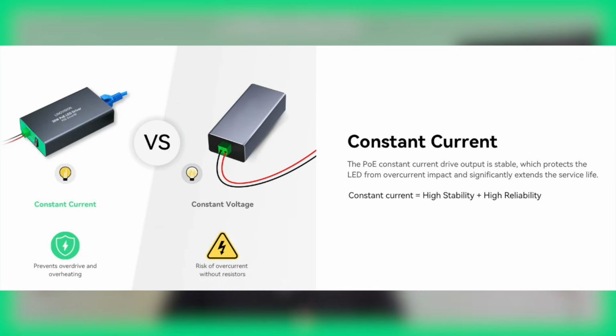LEDs driven at constant current maintain more constant output across their operating range, respond more predictably to dimming control, and degrade more uniformly over time, which is what keeps fixture-to-fixture consistency intact over the life of the installation.